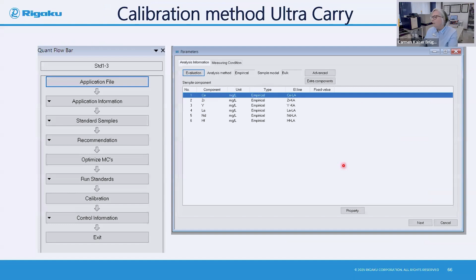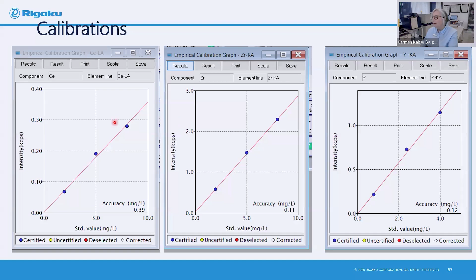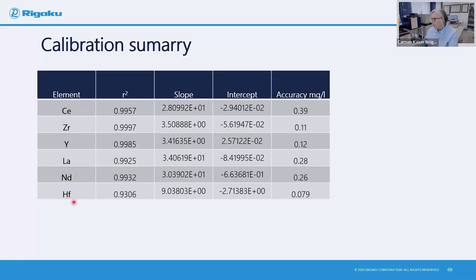And you can see that we can set up these elements very nicely using this ultra carry method, which is known as our pre-concentration method. Some more examples of calibrations. You can see some summary of the calibration. You can see that we can very nicely set up a good correlation with a good accuracy shown in ppm for these elements that you see here in the liquid samples.